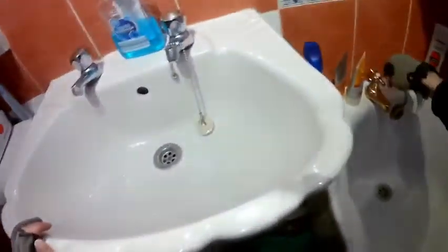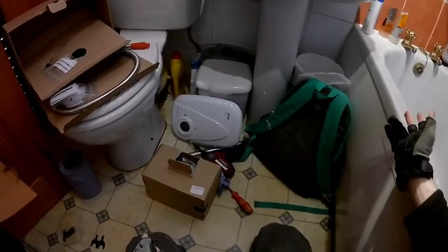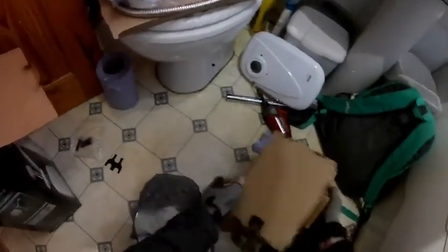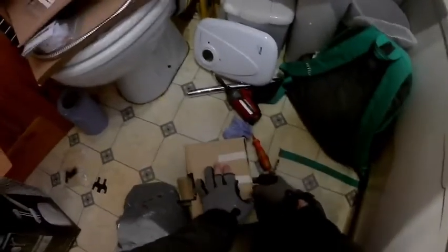It's so that you've got the versatility of being able to use surface mounted connections where you've got the landlord special where they've drilled two holes in the ceiling and run two chrome 15 mils down. You can just push those directly onwards, although you do need to rough up the chrome, I think, although you technically don't, but I think you do, to help the jaws on the connections inside fit, because they're like speed fit connections, and anybody that's worked with chrome, you don't really want to push a chrome pipe into something like a speed fit elbow.